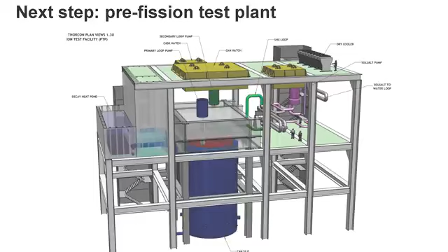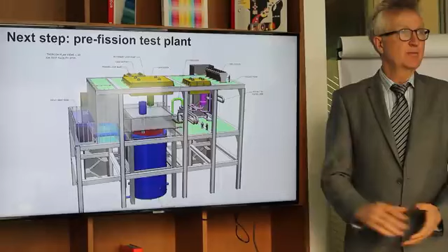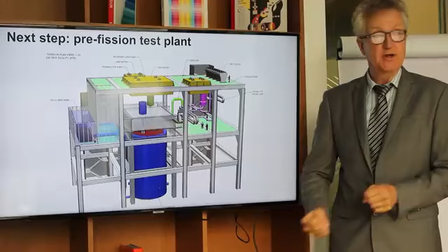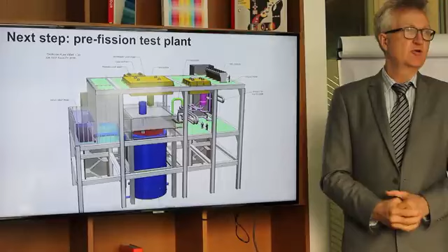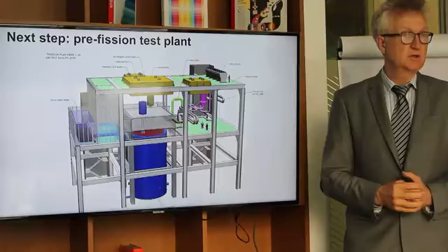This is a test plant full scale. It uses electricity for heat since we don't have any fission, around 10 megawatts of heat. We can use that to run the pumps at 120% of full speed and verify that we don't get any vibration in the pipes, that everything is snugged down appropriately with the right kind of shock absorbers. We can even emulate accidents. For example, drain the salt and turn the heaters on that are in the drain tanks to mimic the heat that's generated by decay heat and verify the cold wall will extract that decay heat and send it up to the decay heat removal pond.